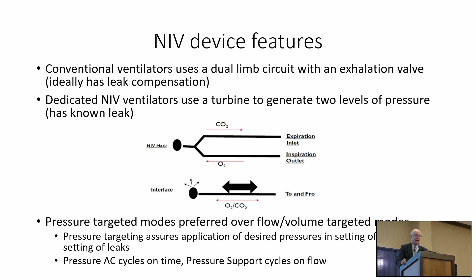Dedicated NIV ventilators are a little simpler. They use a single limb, and it's usually a turbine or some form of compressor that generates two levels of pressure, and a leak is built into the system. So it's a flow-through system, if you will, with higher pressures during inspiration, lower pressures during expiration. And this is an easier system to build. Leak management is easier with these kinds of systems, and these are the systems that normally would end up in somebody's home. We tend to use pressure-targeted modes rather than volume-targeted modes. These are a little easier to deal with in these single-limb circuits. Dealing with leaks is a little bit easier. And I'll put my prejudice in here: pressure-targeted modes tend to be more comfortable. The two common modes are pressure-assisted control, which cycles on a timer you set, or pressure support, which cycles on a flow measurement.